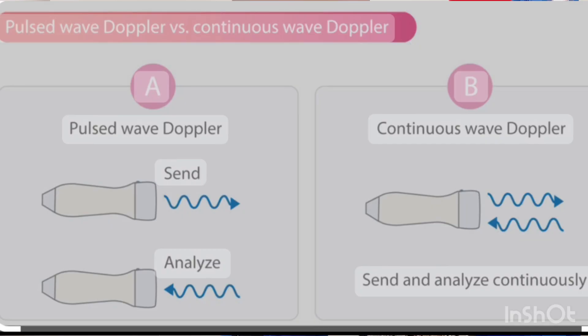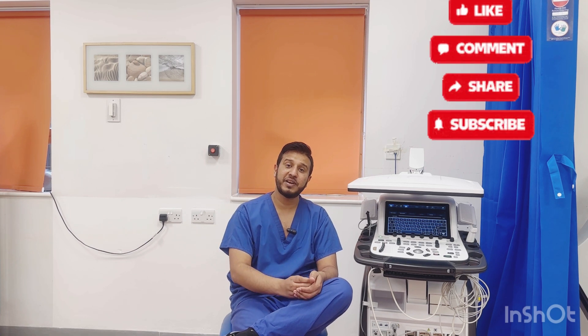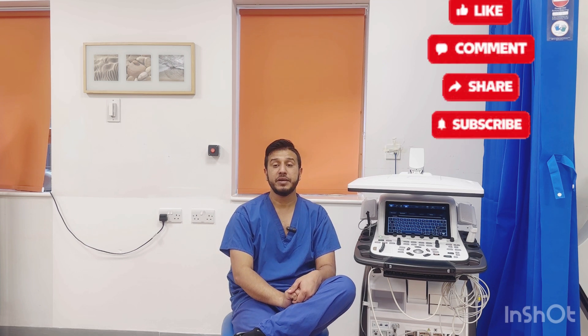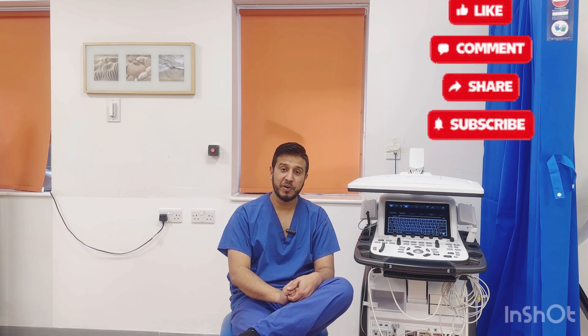In pulse wave Doppler, only one crystal is used, which works both as a sender and as a receiver — it first transmits a signal, then receives it. Because only one crystal is used, there is a delay in pulse wave, and there is a Nyquist limit. The Nyquist limit is the highest velocity you can achieve using pulse wave Doppler — you can't get the highest velocities through it.